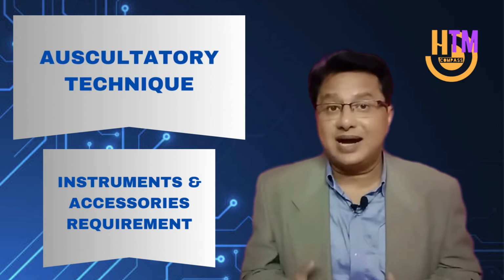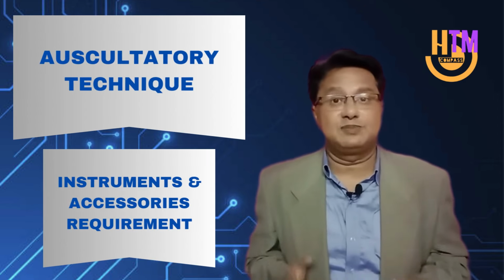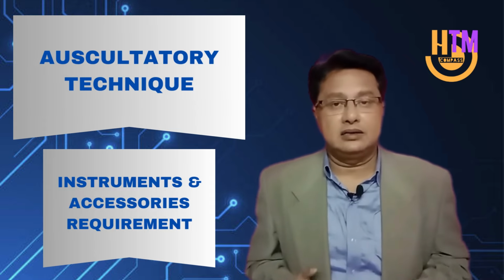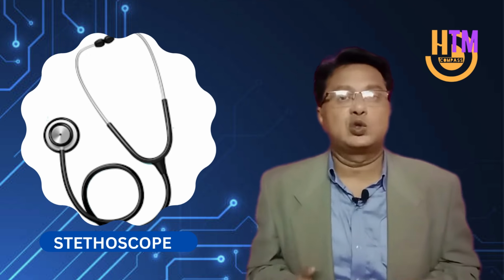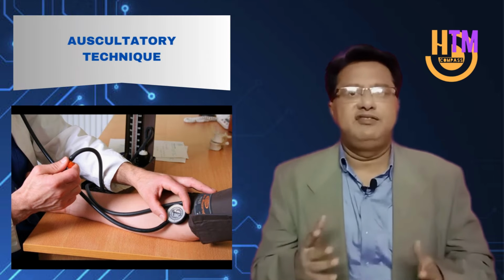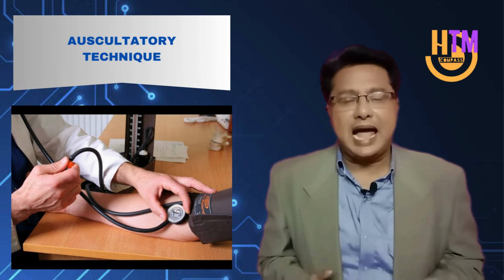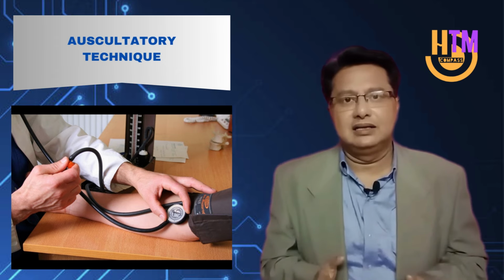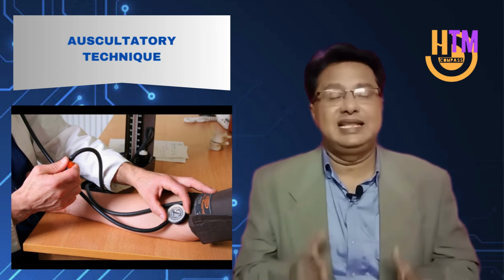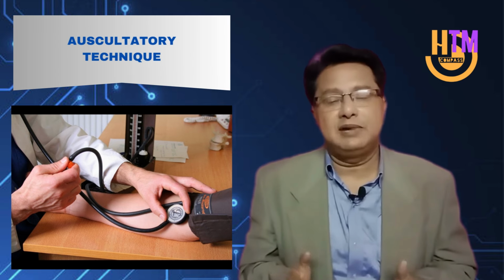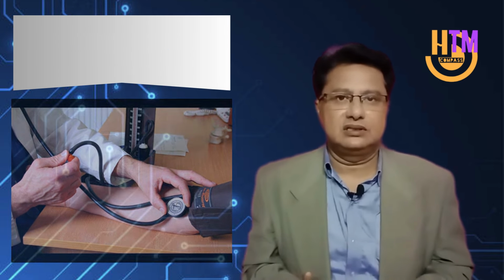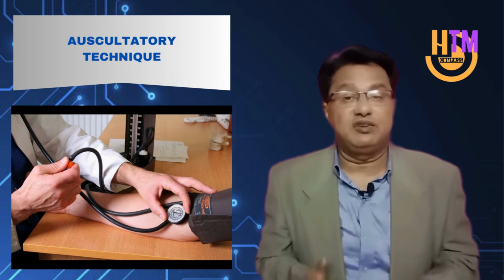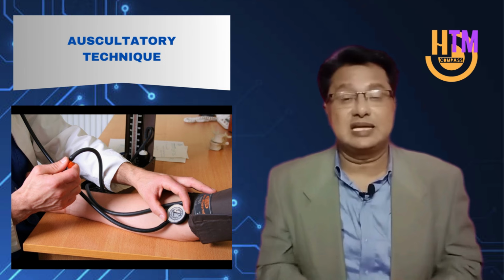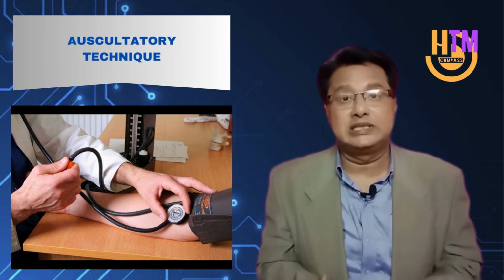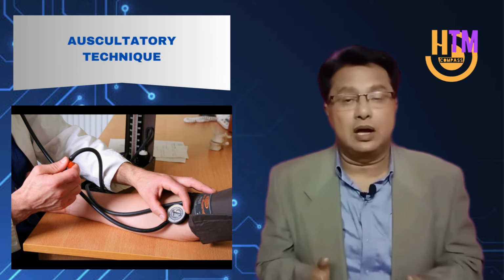The auscultatory method requires some instruments and accessories to get this blood pressure monitoring done. And those are the sphygmomanometer, the stethoscope, the inflatable cuff, and the rubber bulb. The inflatable cuff is wrapped around the upper arm, and it is kept at the same vertical height as the heart. There are 2 tubes with this inflatable cuff. One goes to the rubber bulb and another goes to the sphygmomanometer. The rubber bulb is squeezed repeatedly in order to inflate the cuff, and when the cuff pressure reaches the same level as the arterial pressure, it occludes the arteries, and there is no blood flow at all.